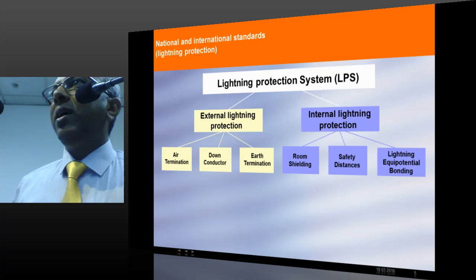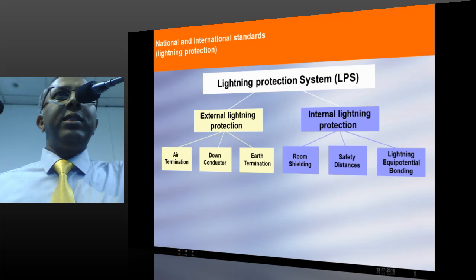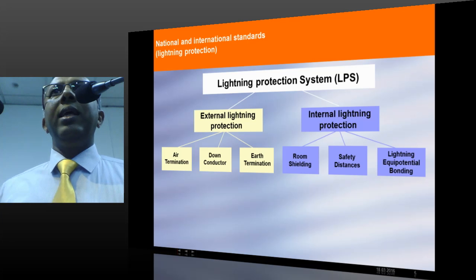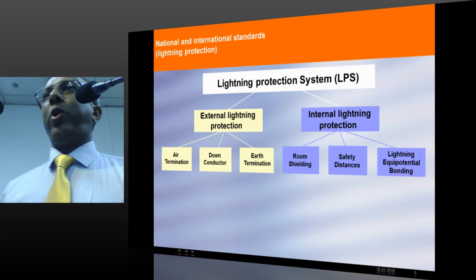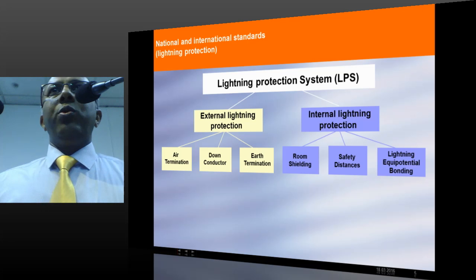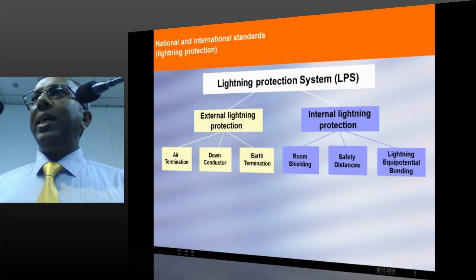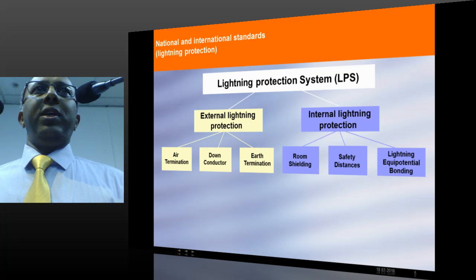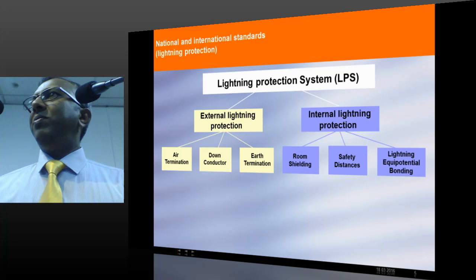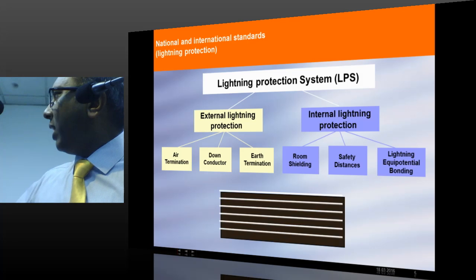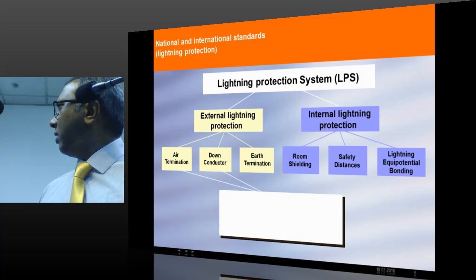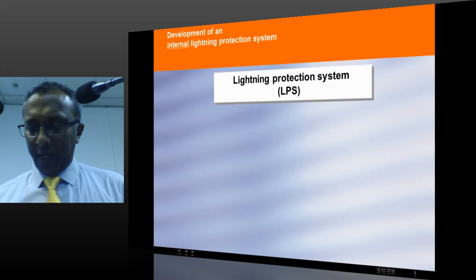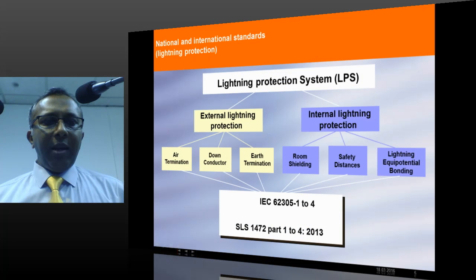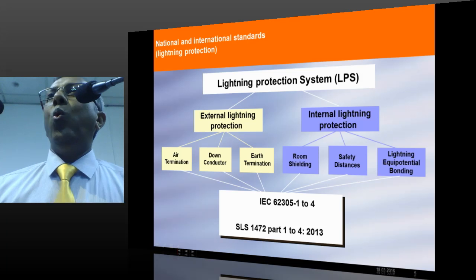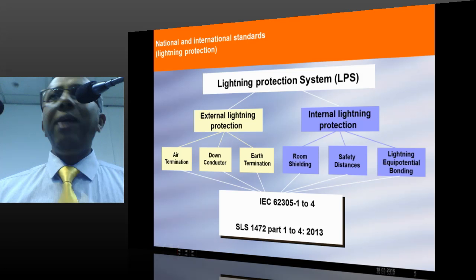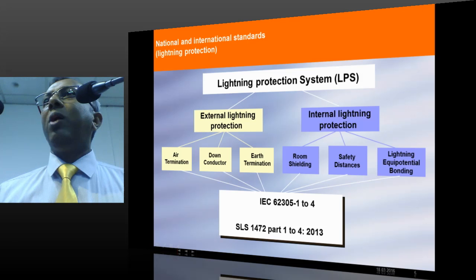See, once when we talk about lightning protection, people always say, okay, there is a rod or maybe an air terminal, and then the second point which we think of is a surge protection device. So generally in the market, people think that an air terminal as well as a surge protection device will do the whole protection. This is a belief all over Asia, which is not true. Air termination is only one of the subjects. If you have a very good air termination and you don't have proper down conductors, then you are in trouble.